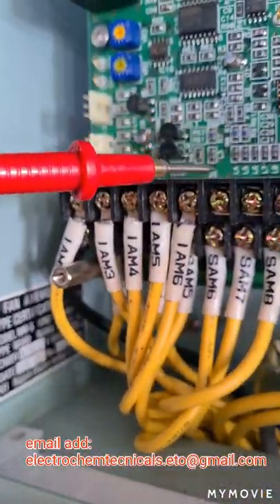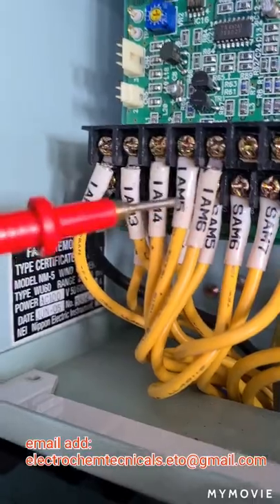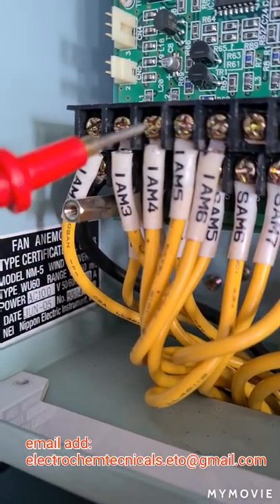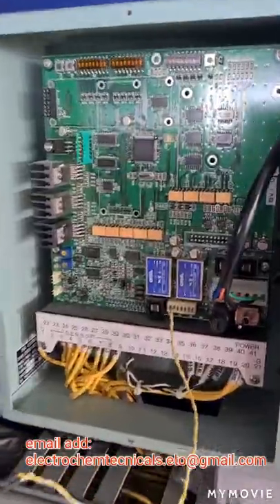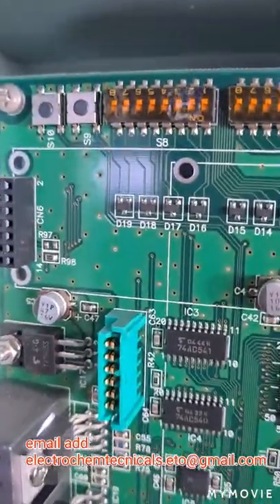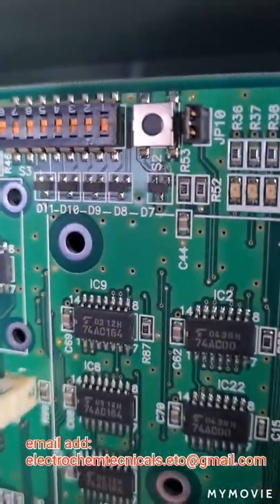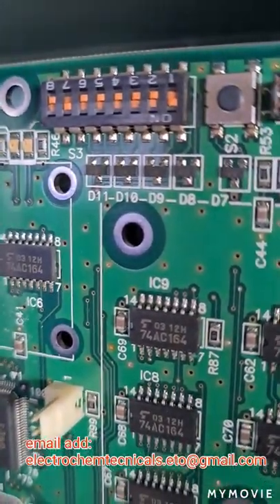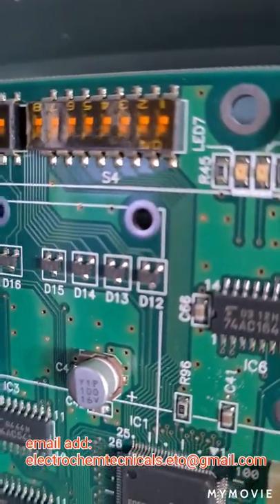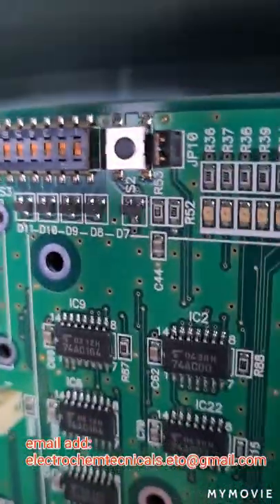And as I verified also, terminals 26, 25, 24 are the topmost part of the terminal block provided on the PCB of my converter. I am doing a further check, one by one, of each component: the capacitors, the ICs, the diodes, any trace of discoloration of contacts and components inside the PCB, the dip switch settings, and the soldered components, and I observe all of them are in good condition.